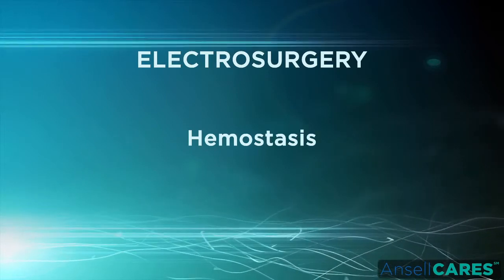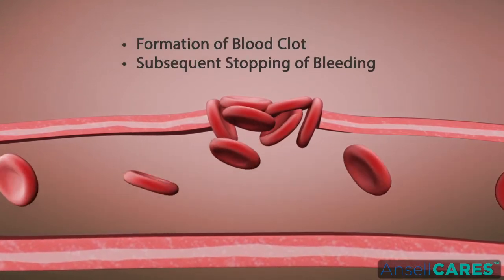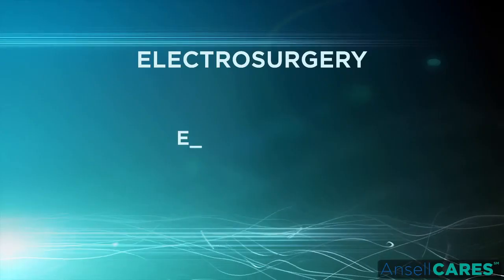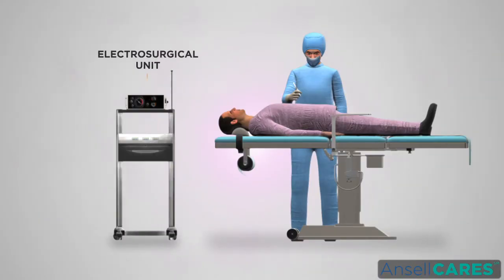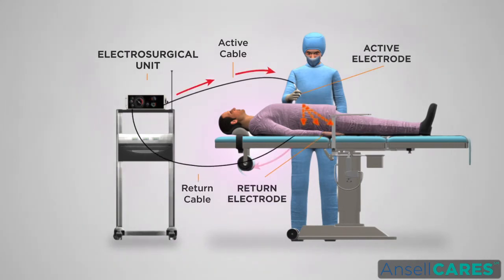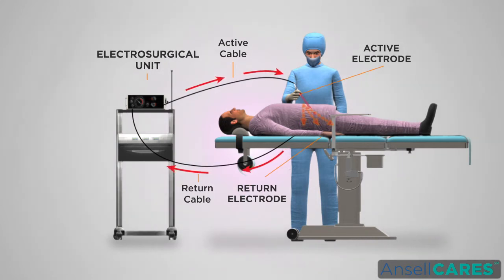Hemostasis is a process of formation of a blood clot and subsequent stopping of bleeding. Electrosurgery is the application of electrical current to biological tissue. A complete circuit must exist for electrical energy to flow. Three basic system components are needed: a power unit, an active electrode, and a dispersive or return electrode.